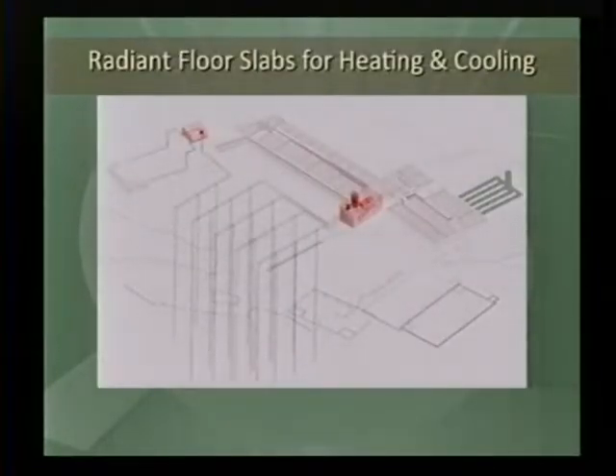And this is a little bit of a faint diagram, but there are 16 wells for the main building and 6 wells for the conference wing, those are in this area here. All the wells go down about 225 feet. The mechanical mezzanine in the conference wing, and the lines for the fin tube convectors for heating. The cooling coil with the ventilation system is in that unit. Here's the 500-gallon tank. And you can see that the radiant slab has a number of different zones. The area where there is not any radiant slab heating is right here.